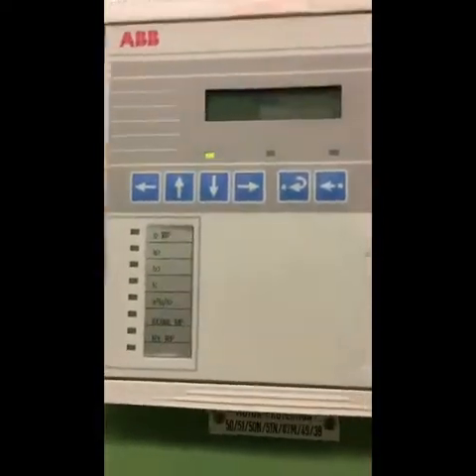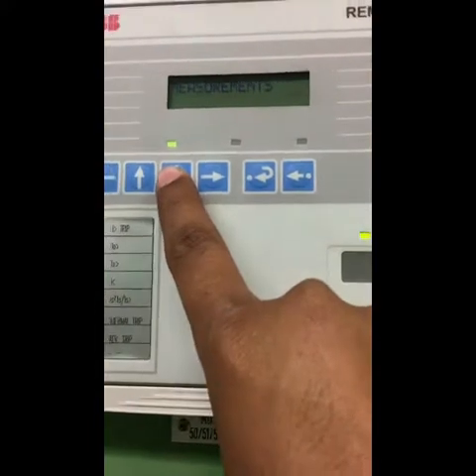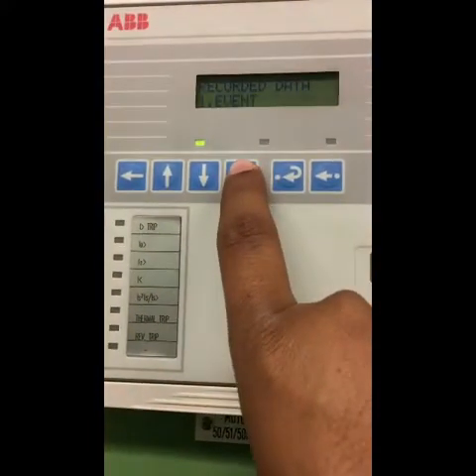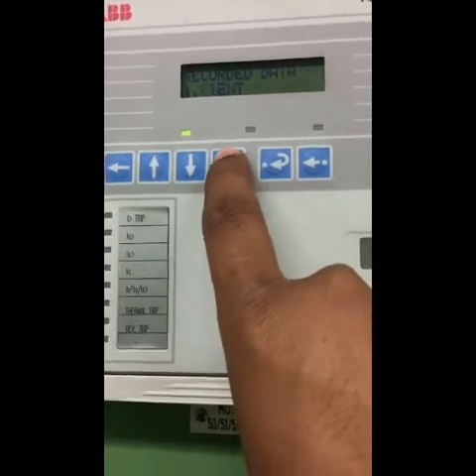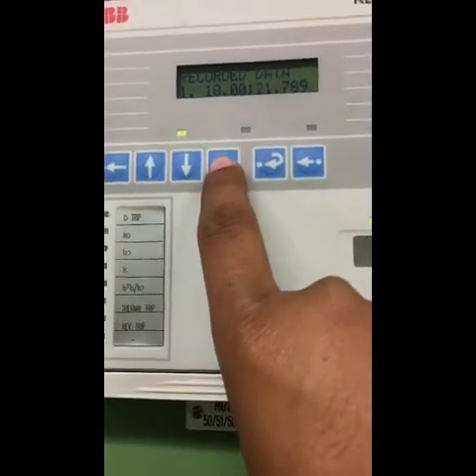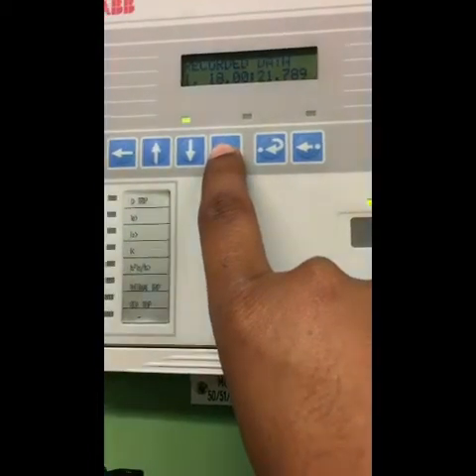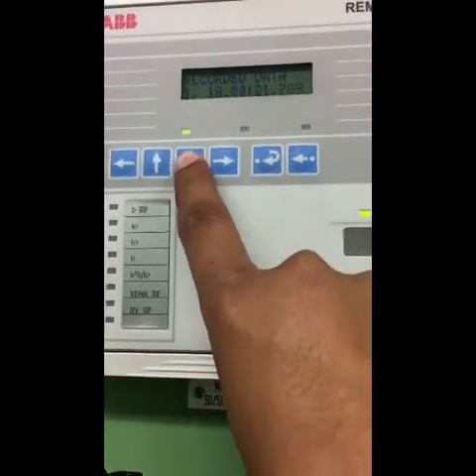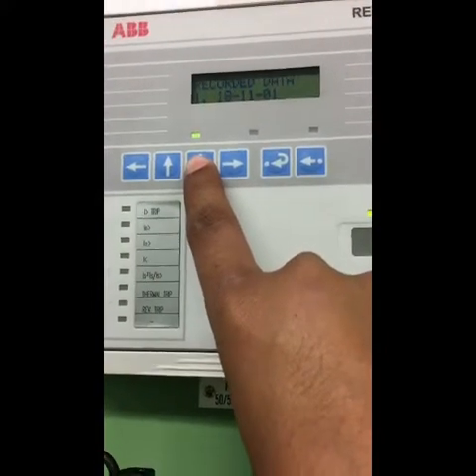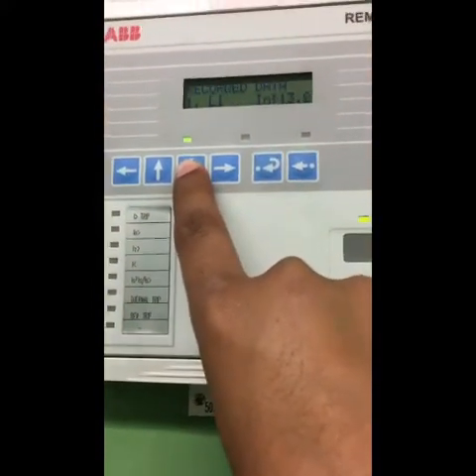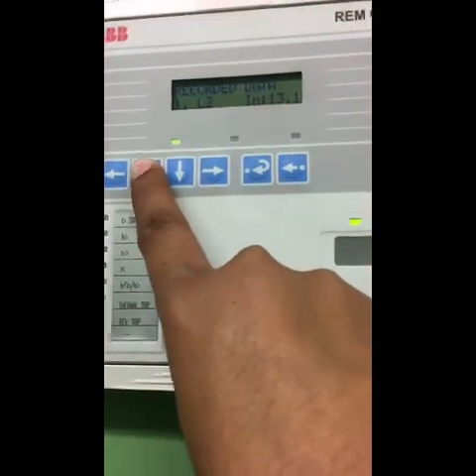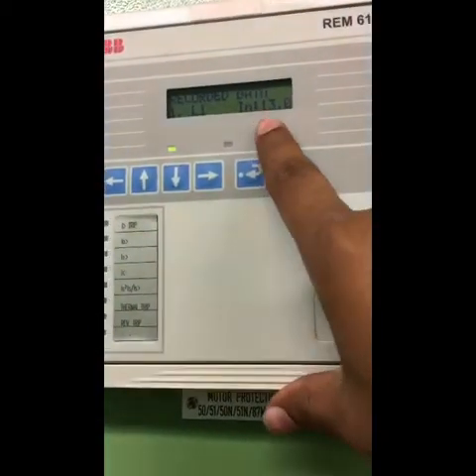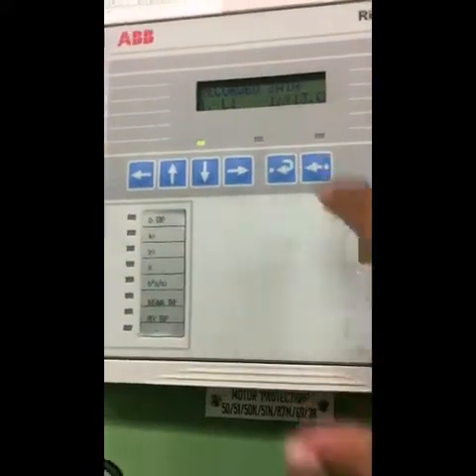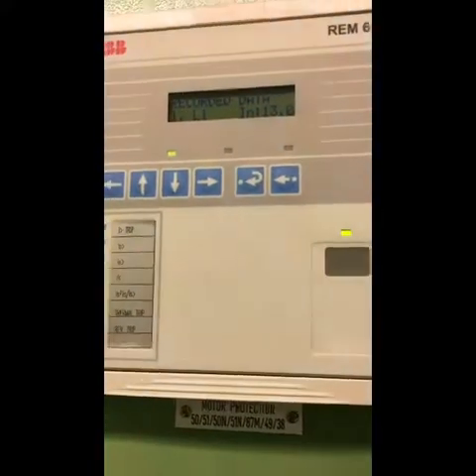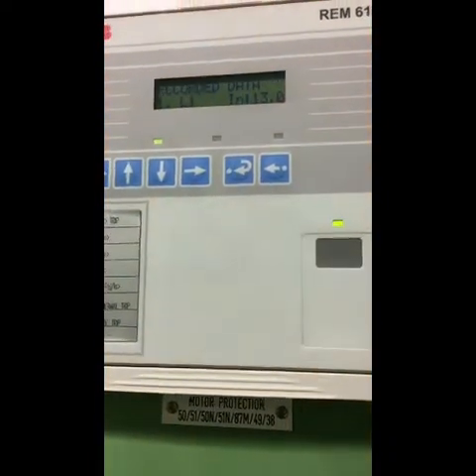To read more details about the fault, we will go down to record the data, event. This is the time of tripping. I just gave the signal, so the time now is 6 o'clock. The date, 1st of November 2018. And these are line 1, line 2, line 3. What happened is 13 times the rated current, 13 times the secondary of the CT, which is 1. So 13 by 1 to the primary.